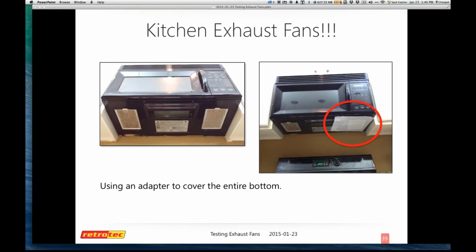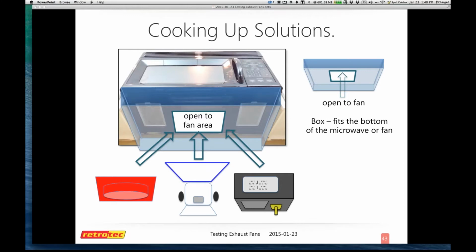So the method on the right, I should change this line and say, is not the way you should do it. Everybody says, oh, I saw this, that's not a good method. And that is correct. Some of the illustrations I tried to do were showing what your results were. Trying to do a method where you close off one side to read the other will not give you accurate results.